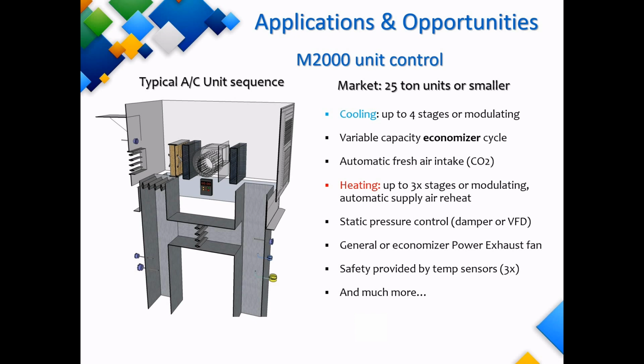Prolon's rooftop controllers are best suited for units up to 25 tons, such as we would see in most light commercial buildings. We can control units up to 50 or 60 tons. However, sometimes an additional controller is needed to be able to monitor and control all components. For the cooling, the M2000 can control up to 4 stages of cooling. In most units smaller than 25 tons, 2 stages is the standard. But for those larger units, we can control up to 4 stages.